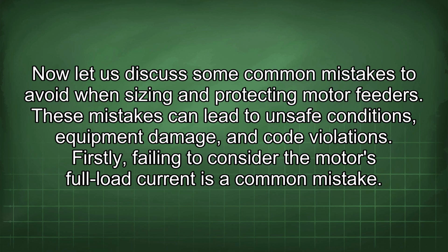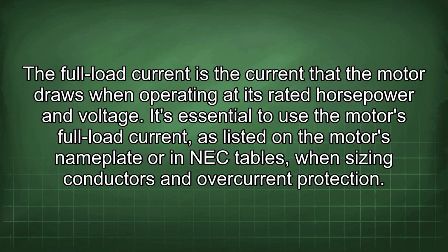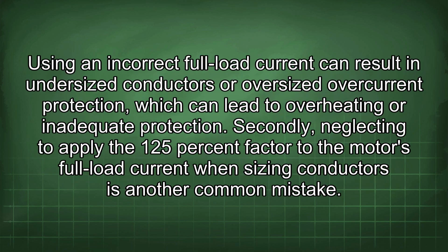Firstly, failing to consider the motor's full load current is a common mistake. The full load current is the current that the motor draws when operating at its rated horsepower and voltage. It's essential to use the motor's full load current, as listed on the motor's nameplate or in NEC tables, when sizing conductors and overcurrent protection. Using an incorrect full load current can result in undersized conductors or oversized overcurrent protection, which can lead to overheating or inadequate protection.